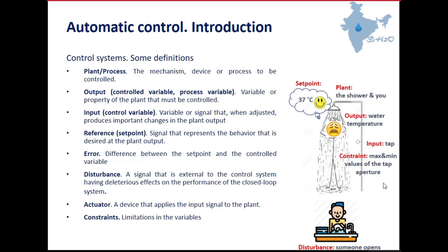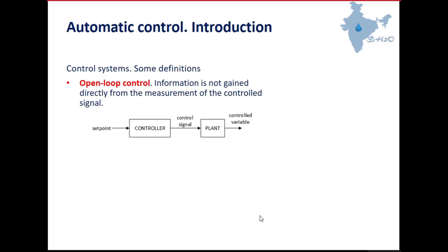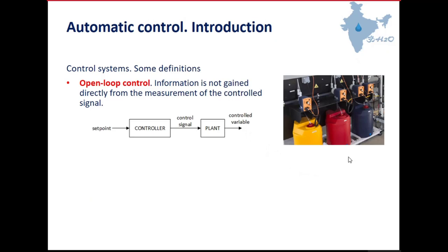Now let's see the difference between open loop control and closed loop control. In open loop control, information is not gained from the measurement of the control signal. We have our set point, our controller gives a control signal, and then we have our controlled variable. An example is dosifier pumps used in pre-treatment in water treatment plants, where you choose the quantity of doses to apply by changing buttons but you don't measure whether the flow is correct — you trust the dosifier pump. This is open loop control.